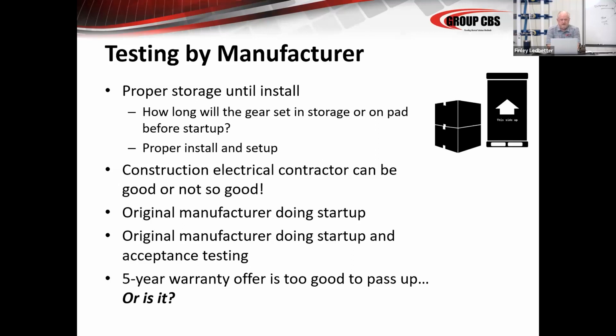Another reason that the manufacturers want this 5-year warranty or want to do this acceptance testing in this startup is when they find a deficiency or a problem, they behind the scenes sometimes can deal with the issue before it's really brought to your attention. So watch that pretty closely.